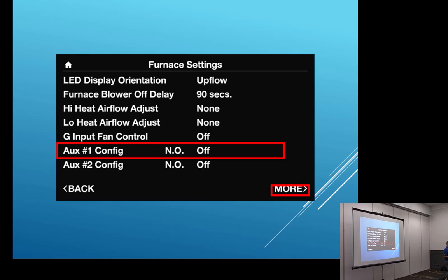Our furnace settings, you can come in here to furnace. If you have a furnace or an air handler, you come into here. This aux1 and aux2 configuration here, this is where we set up our float switch. Okay? On the new boards now, it doesn't say aux1 or aux2 anymore because some government entity told the manufacturers they had to have a designated condensate switch, a designated water circuit switch. You couldn't say auxiliary. It had to be designated that. So now on the new boards, it says common and CS for condensate switch.